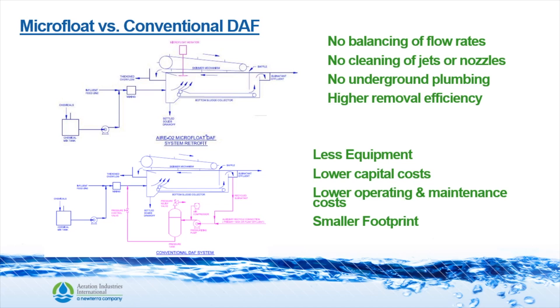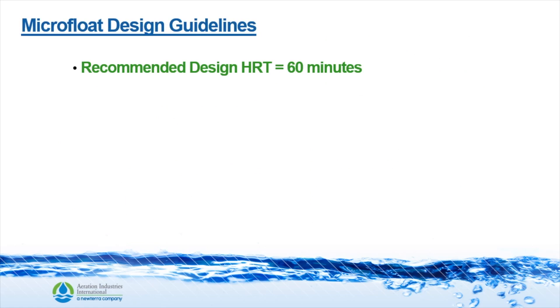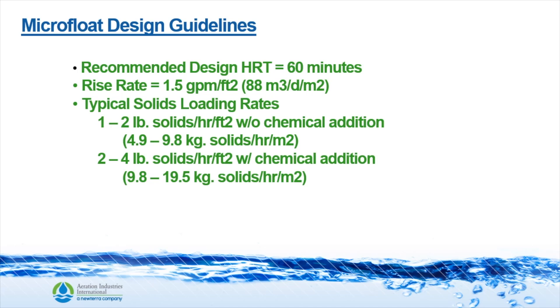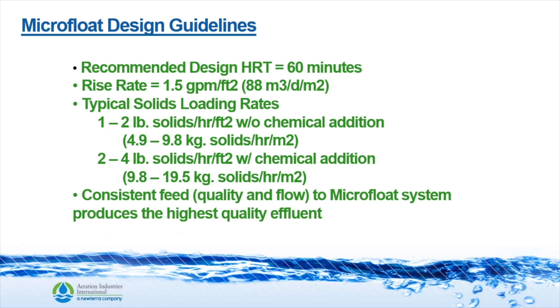This is much more complicated and requires flow balancing and has extra piping and valving. Now I'd like to talk about some of the microfloat design guidelines. We recommend that you have a hydraulic retention time of 60 minutes and a rise rate of 1.5 gallons per minute per square foot. Typical solids loadings are 1 to 2 pounds per hour per square foot without chemical, or 2 to 4 pounds per hour with chemicals. We also know that you get the best consistent effluent if you have a consistent feed, flow rate, and quality.